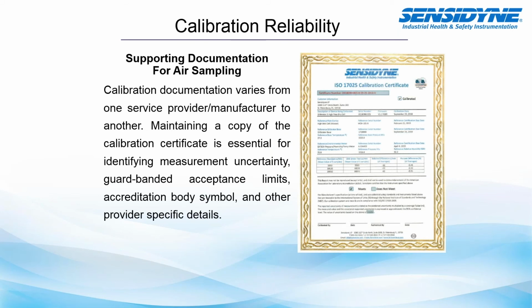So additionally, supporting documentation will include the calibration certificate. Calibration documentation varies from one service provider or manufacturer to another. Maintaining a copy of the calibration certificate is essential for identifying measurements of uncertainty, guard-banded acceptance limits, accreditation body symbols, and other provider specific details.